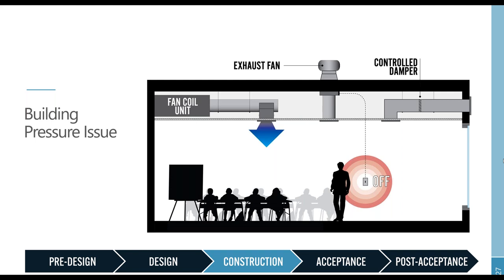So this began months before they were trying to get their occupancy, when we were just doing some preliminary spot checks and testing. The way that this room is designed is that we have air coming into the space with a fan coil unit providing conditioned air. But because it's a science classroom, at the teacher's desk there is a switch that allows for an exhaust fan to turn on so that they can exhaust any little experiment that they might be doing at the front of the classroom. However, when that switch is tripped on, the intent is that these control dampers open up to allow air to come in so that we don't change the pressure of the room. And we allow just as much air to come in as is being exhausted by this fan.